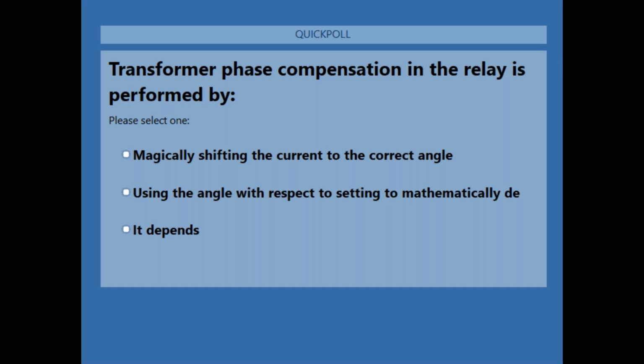the poll question is, transformer phase compensation in the relay is performed by A, magically shifting the currents by whatever angle we need to, or B, figuring out how the transformer is wired based on the angle with respect to setting and calculating a compensation matrix using all the currents that are wired to do phase compensation, or C, it depends, right? So there you go. There's your depends again.